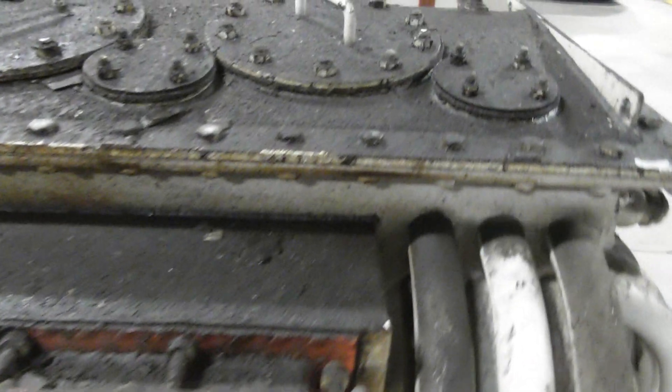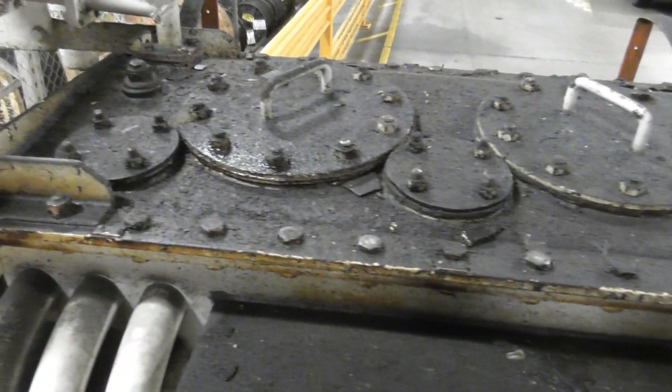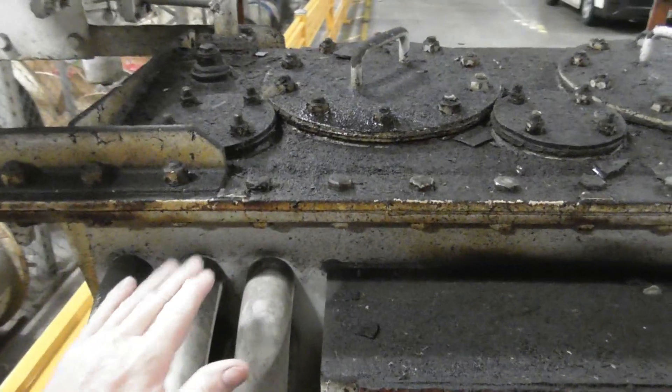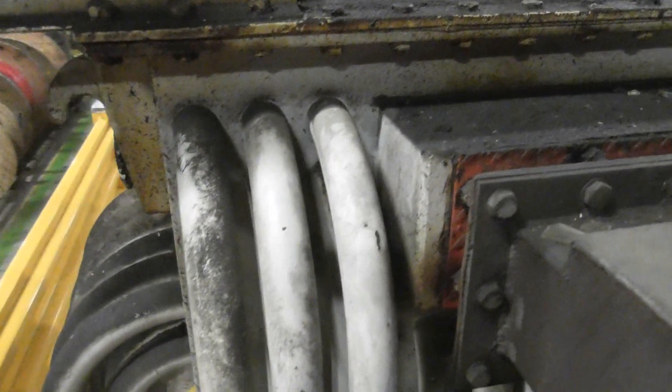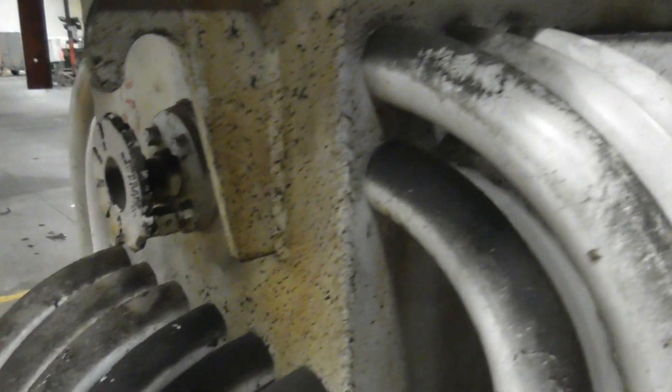There's a PILC cable going in there. Look at this — you've got access hole covers here in the top, so you drop the oil level below the top lid and you can get access to the terminals. I'll also have a look at the tap changer and hopefully get the nameplate.